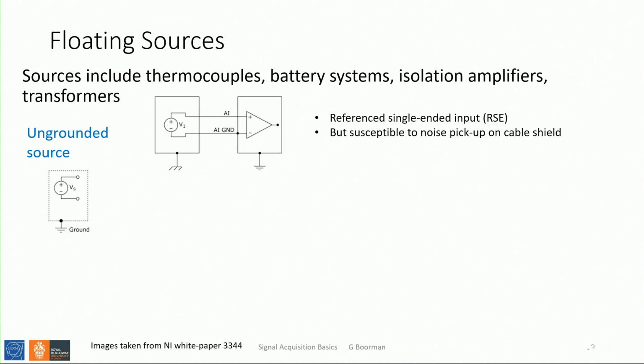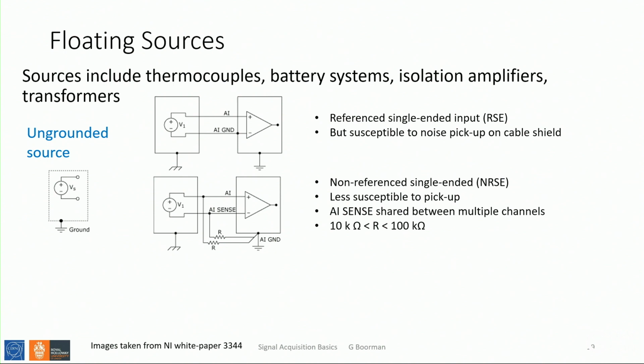So you can do something like this. This is a single-ended input, and you don't have a ground loop, because the ground loop is broken: the signal source is not connected to that little earth symbol there. So again, you won't have a ground loop. You can do that, but you can pick up noise on the cable shield. Careful routing of your signal source can help eliminate that. My preference is to do this or the next diagram. This one uses the analog input sense, and you need to reference that to something, so you use resistors to ground. If you follow the instructions at the back of the datasheets, you generally won't go far wrong.